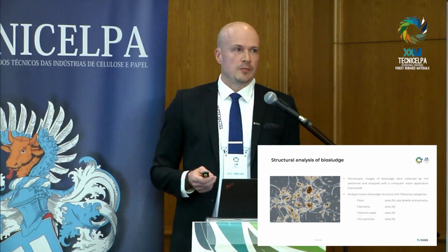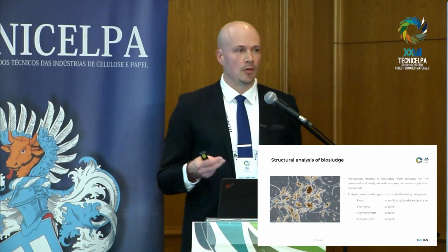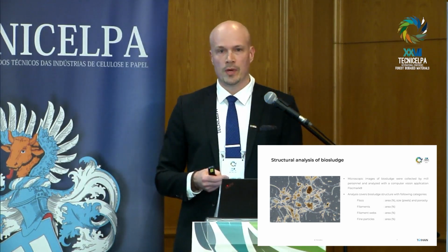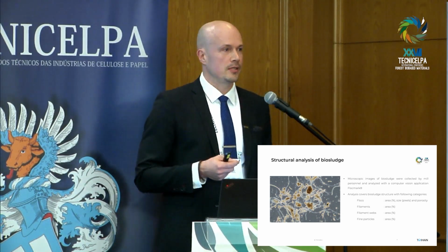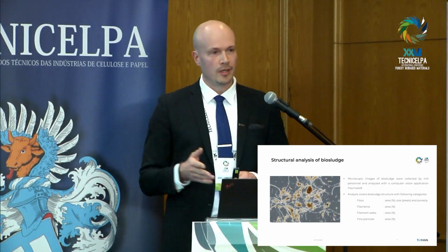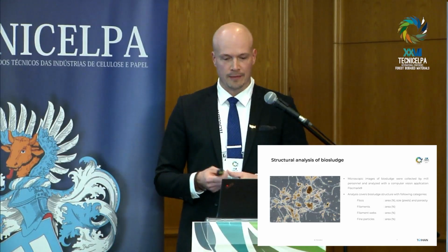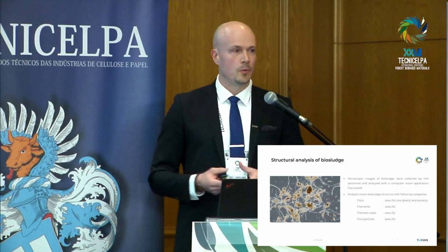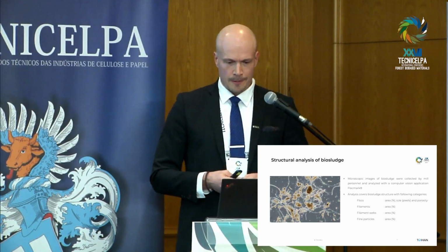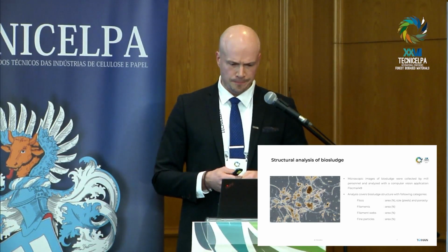And why I chose this process shutdown, production shutdown time period, is, of course, because we see a lot of changes in biosludge when we don't have incoming wastewater. The biosludge that has been grown in the aeration basin stays in rotation, and it starts to decay by microbial activity. So we see the structural change. This makes it very interesting to apply computer vision over production shutdowns.